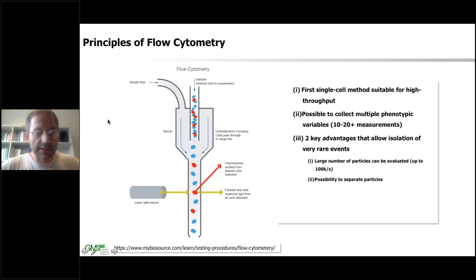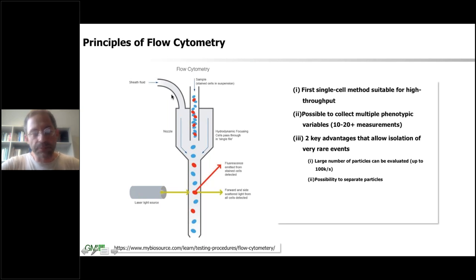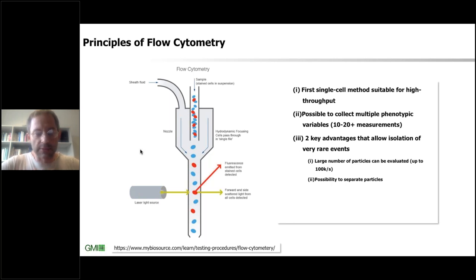Let's look straight into the heart of a flow cytometer — that is the flow cell. You can think of flow cytometry really as a stream of rivers. You have a big river here with a sheath fluid that is under pressure and flows with a laminar flow. You have this small river which contains all the particles of interest, injected into the big river, which results in speeding up of the flow and separation of the particles. This is called hydrodynamic focusing, and it results in aligning your particles in the center of the flow stream so you can separate them.